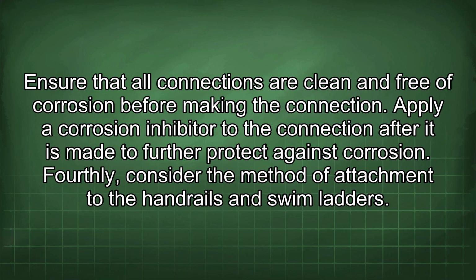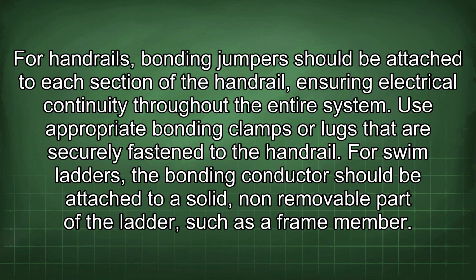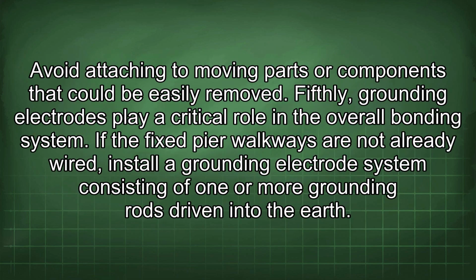Fourthly, consider the method of attachment to the handrails and swim ladders. For handrails, bonding jumpers should be attached to each section of the handrail, ensuring electrical continuity throughout the entire system. Use appropriate bonding clamps or lugs that are securely fastened to the handrail. For swim ladders, the bonding conductors should be attached to a solid, non-removable part of the ladder, such as a frame member. Avoid attaching to moving parts or components that could be easily removed.